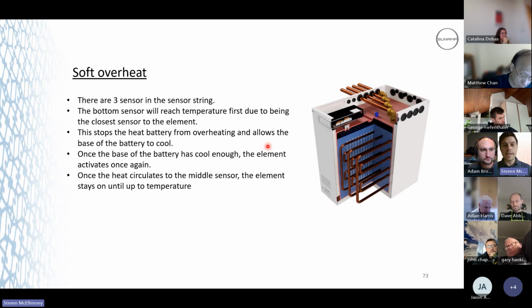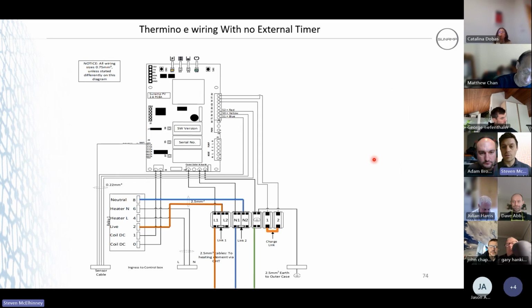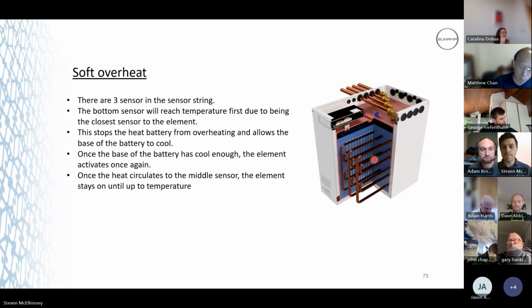The soft overheat, again, you've got your 3 temperature sensors. The bottom sensor will reach temperature first, due to being the closest sensor to the element down here. This stops the battery from overheating and allows the base of the battery to cool on its off cycle. Once the base of the battery has cooled enough, that's a little typo there, the element activates once again. Once the heat starts to circulate around to the middle sensor, the element will stay on until fully up to temperature. And that's your basic sequence operation. Any questions on any of that? All good.